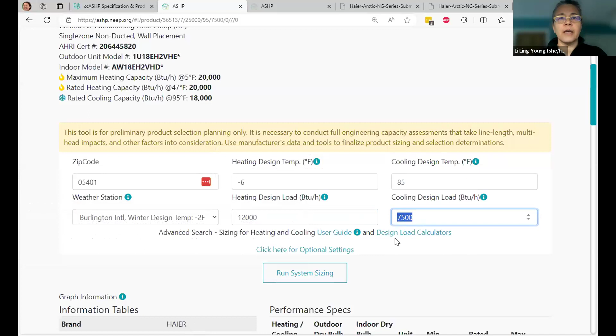This is a ductless heat pump, and I'm not trying to meet the load of the whole building. I'm going to say that the load where I'm putting this heat pump is 12,000 BTUs an hour, so I'll put that in. I'm going to ignore the cooling stuff because we're not going to talk about cooling loads today.